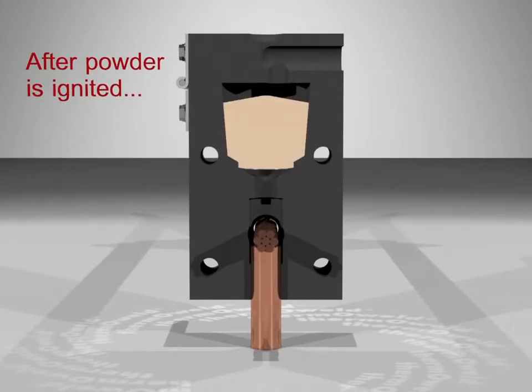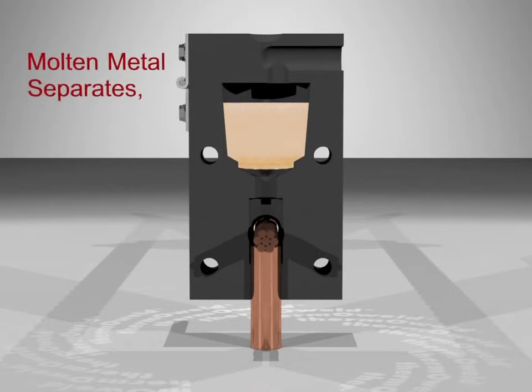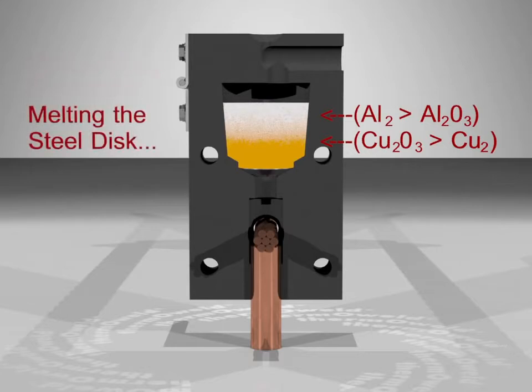The spark from the flint igniter causes a reaction within the weld metal, melting and separating the metals. The molten metal melts the steel disc, allowing it to flow into the weld cavity, creating a permanent connection.